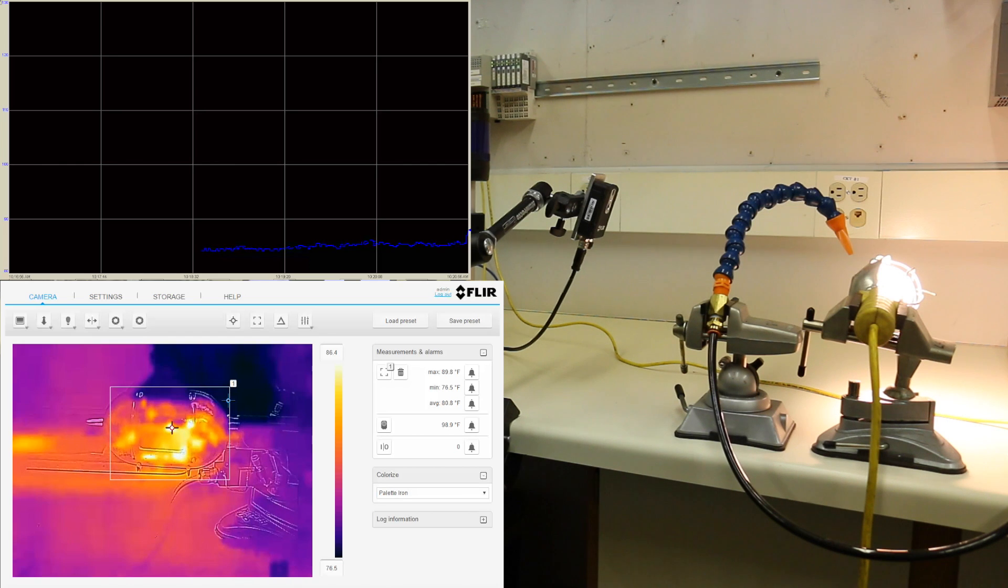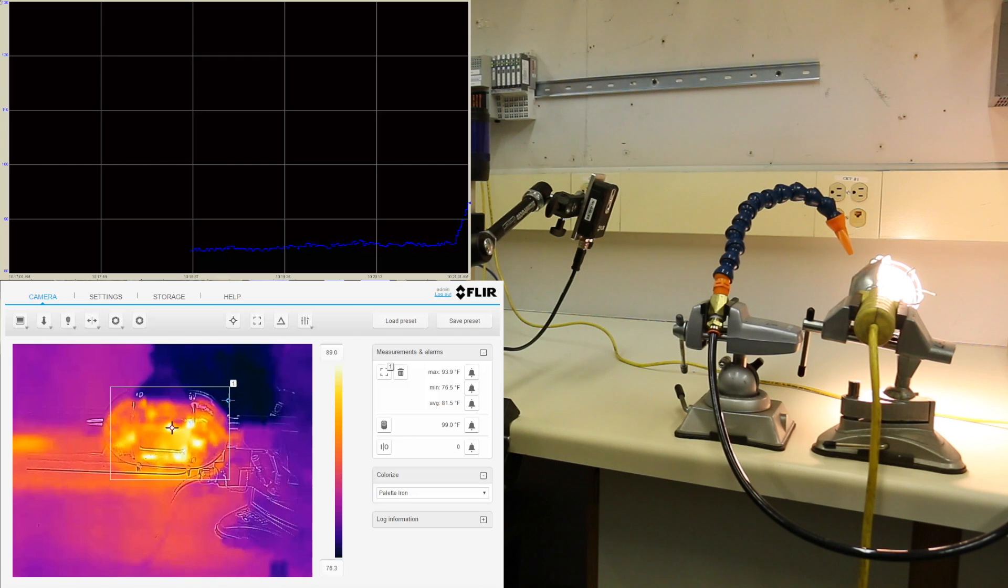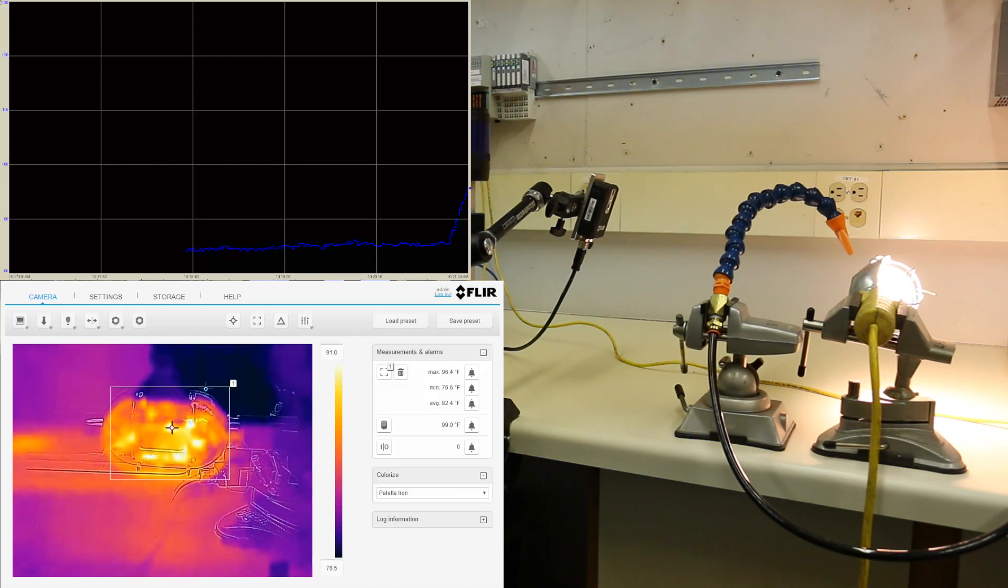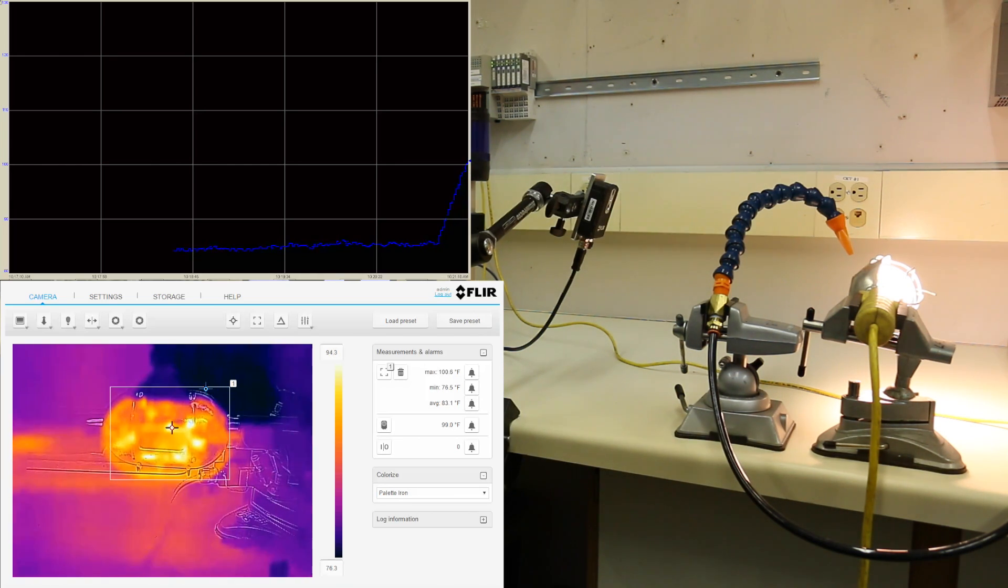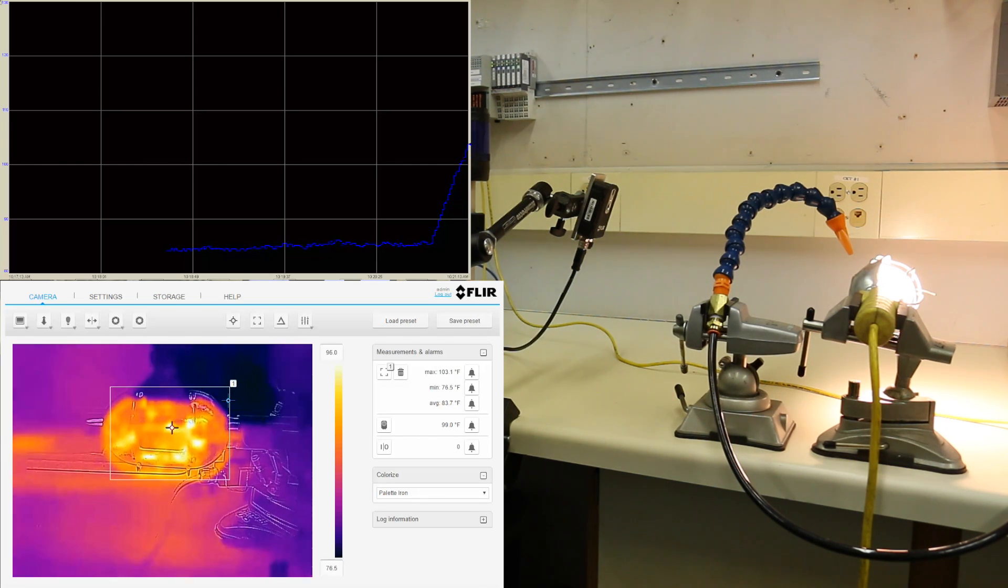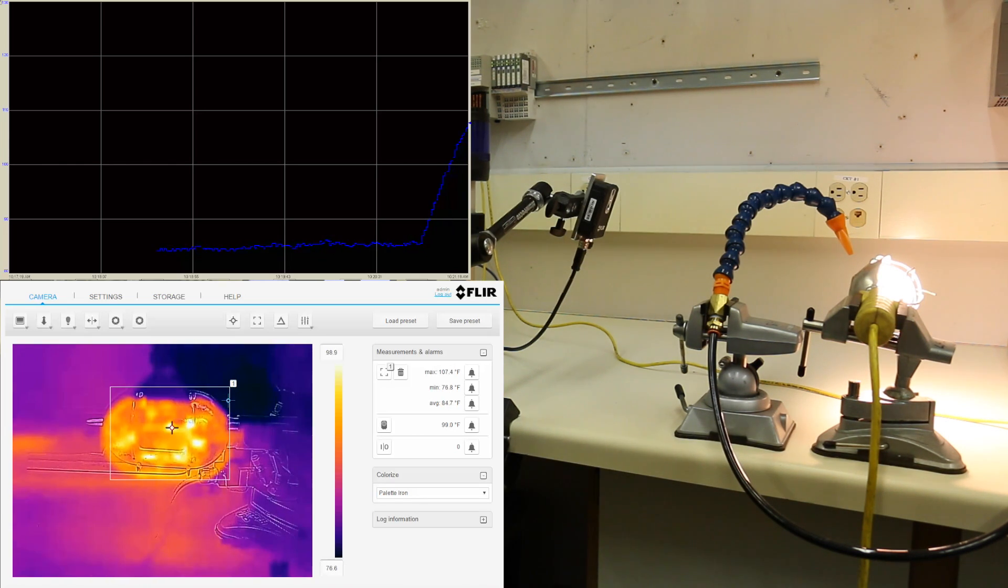If we watch the graph from the PLC, we immediately see that the temperature is rising up quickly on the housing of the enclosure. What makes the AX8 advantageous to a point sensor is its ability to search the min, max, and average temperatures anywhere in the image or specified region like what is shown here.